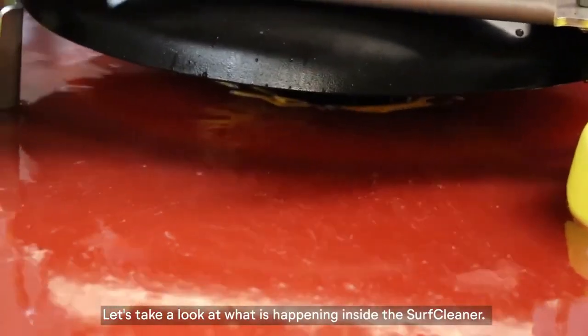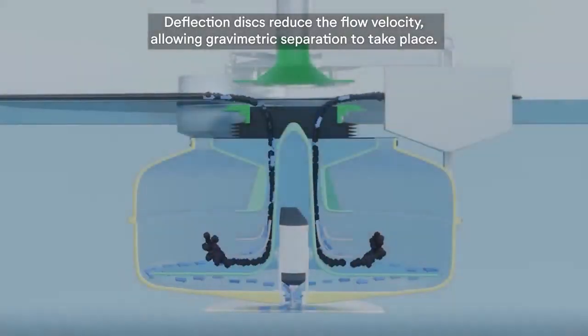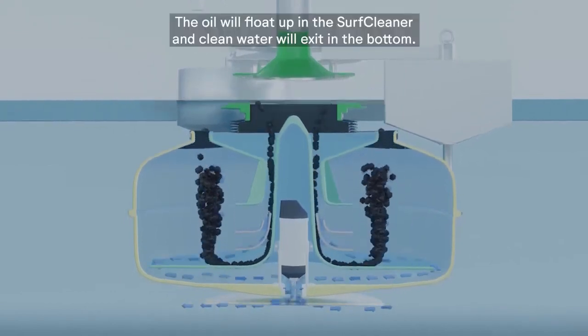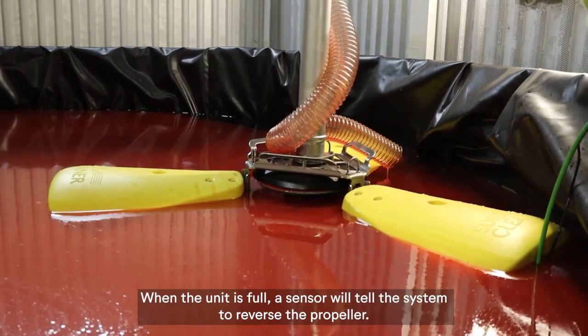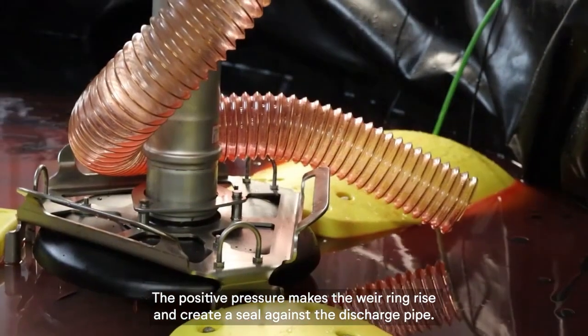Let's take a look at what is happening inside the SurfCleaner. Deflection discs reduce the flow velocity, allowing gravimetric separation to take place. The oil will float up inside the SurfCleaner and clean water will exit at the bottom. When the unit is full, a sensor will tell the system to reverse the propeller.